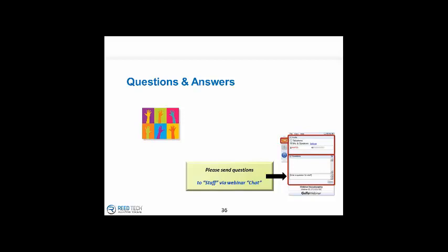So if your number was obsoleted 2 months ago, and you're submitting today, and the FDA now has that updated list from the GMDN that shows your GMDN code obsolete, you'll be refused. So it's a very instantaneous type of update at a 2-week time phase, and you will need to comply with the current GMDN code. So there's no grace period for having an obsolete code for a year.